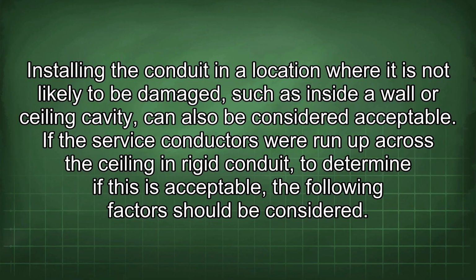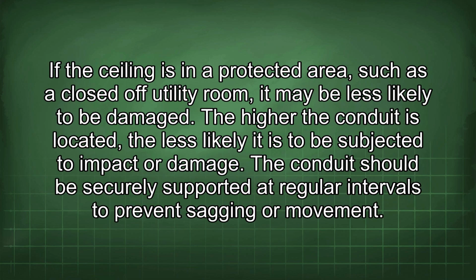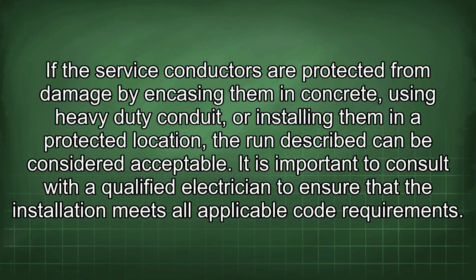If the service conductors were run up across the ceiling in rigid conduit, to determine if this is acceptable, the following factors should be considered. If the ceiling is in a protected area, such as a closed-off utility room, it may be less likely to be damaged. The higher the conduit is located, the less likely it is to be subjected to impact or damage. The conduit should be securely supported at regular intervals to prevent sagging or movement. If the service conductors are protected from damage by encasing them in concrete, using heavy-duty conduit, or installing them in a protected location, the run described can be considered acceptable. It is important to consult with a qualified electrician to ensure that the installation meets all applicable code requirements.